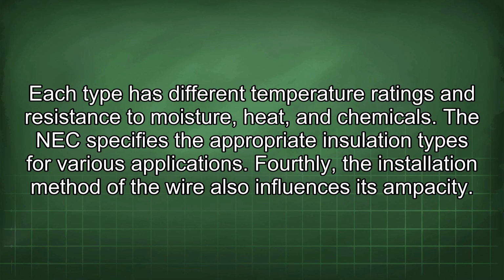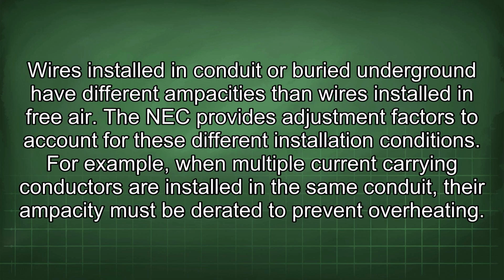Fourthly, the installation method of the wire also influences its ampacity. Wires installed in conduit or buried underground have different ampacities than wires installed in free air. The NEC provides adjustment factors to account for these different installation conditions. For example, when multiple current-carrying conductors are installed in the same conduit, their ampacity must be derated to prevent overheating.